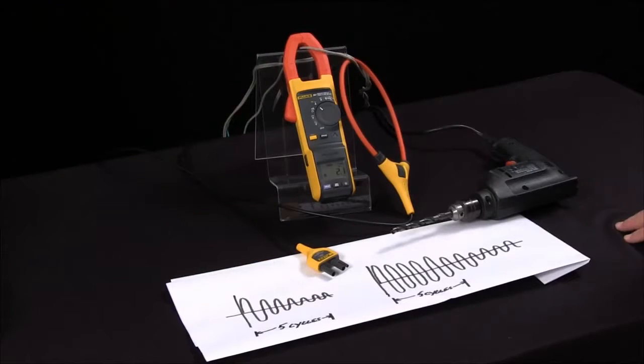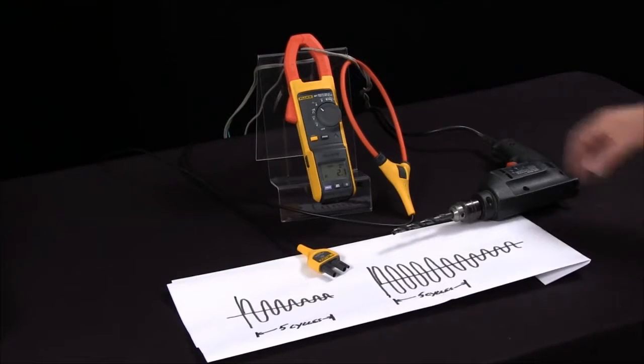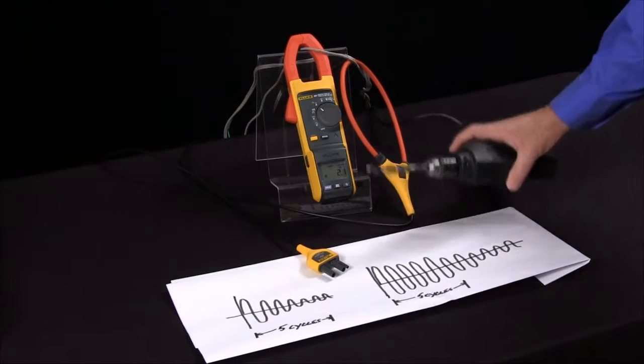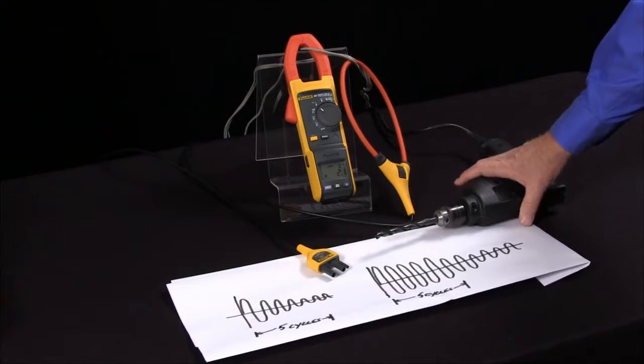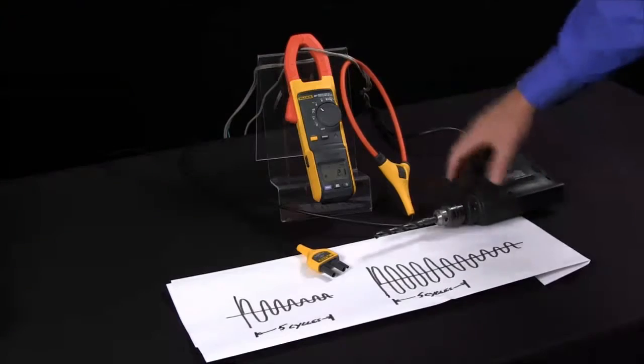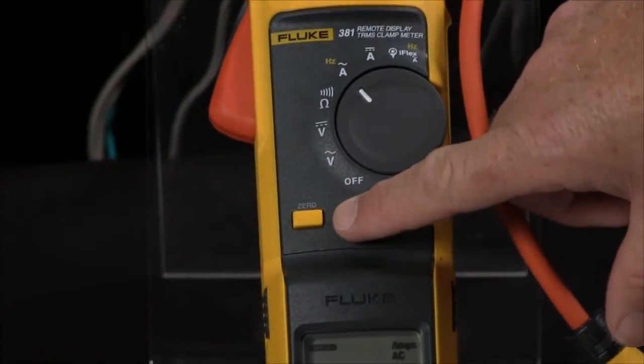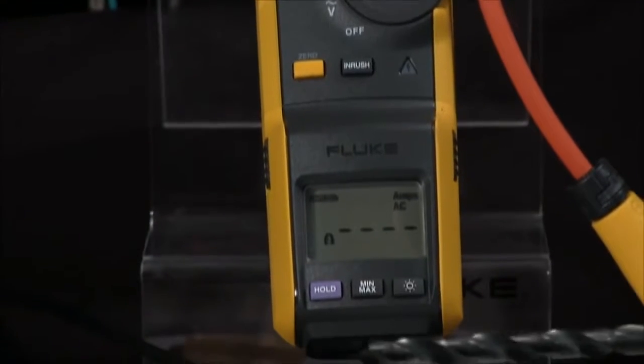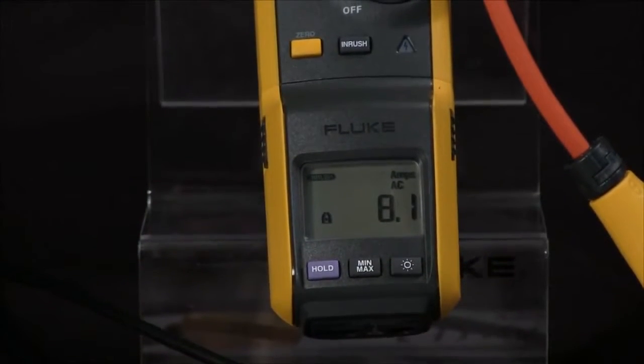How do I measure inrush current with my Fluke 381? To use the 381 to measure inrush current of a motor or other mechanical device, turn it to amps and then press the inrush key. The meter will wait for you to start the motor and will capture the inrush current.